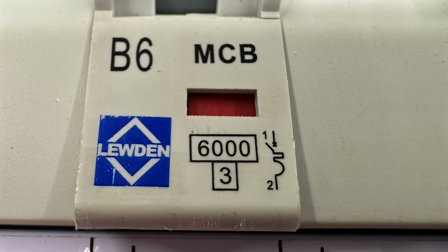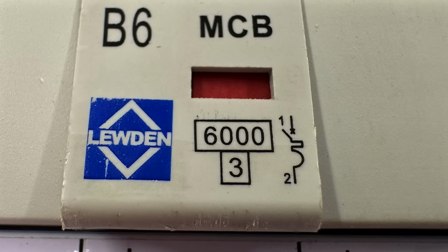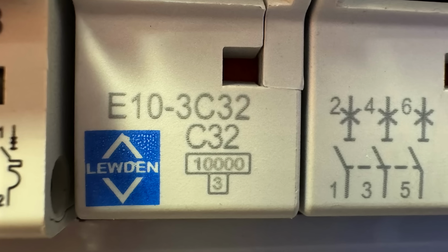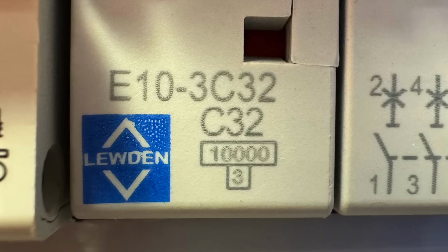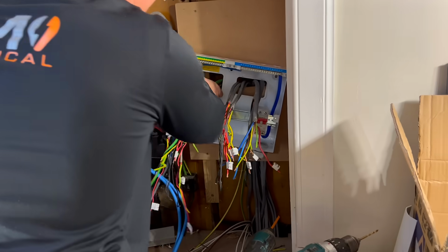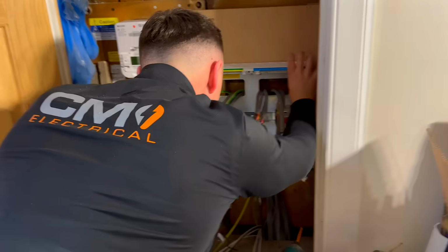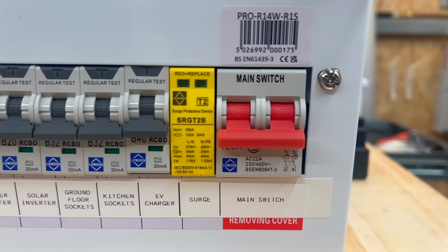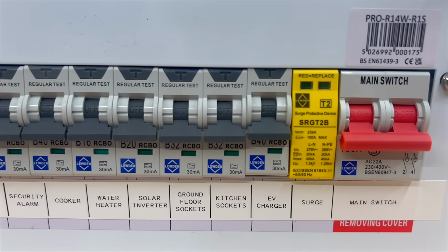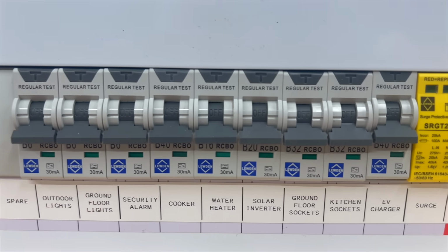The same principle is why consumer units use MCBs rated at 6 kA, while industrial systems require those rated at 10 kA. This solution is ideal for residential installations where surge risks and magnitudes are significantly lower compared to industrial settings. However, it's important to understand its limitations. If you're considering using this board in an industrial application, you may need to reassess your surge protection strategy accordingly.